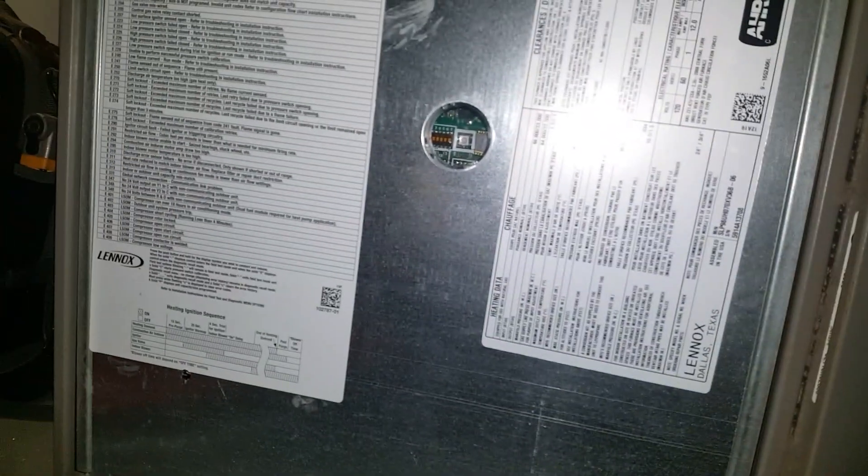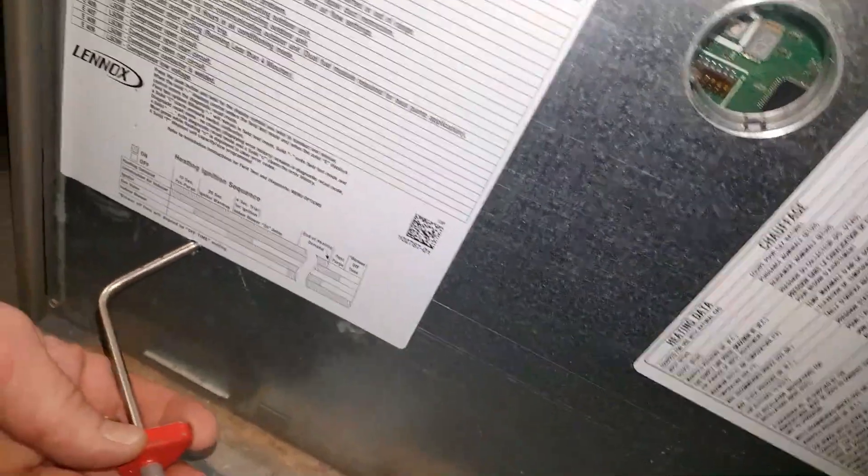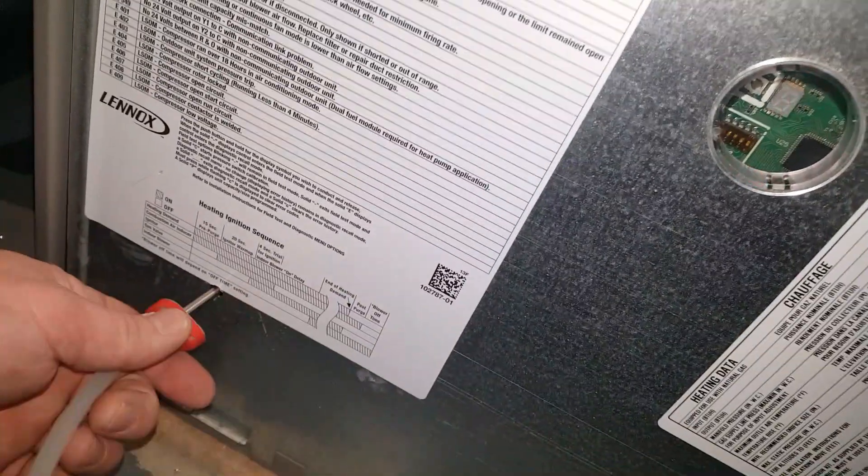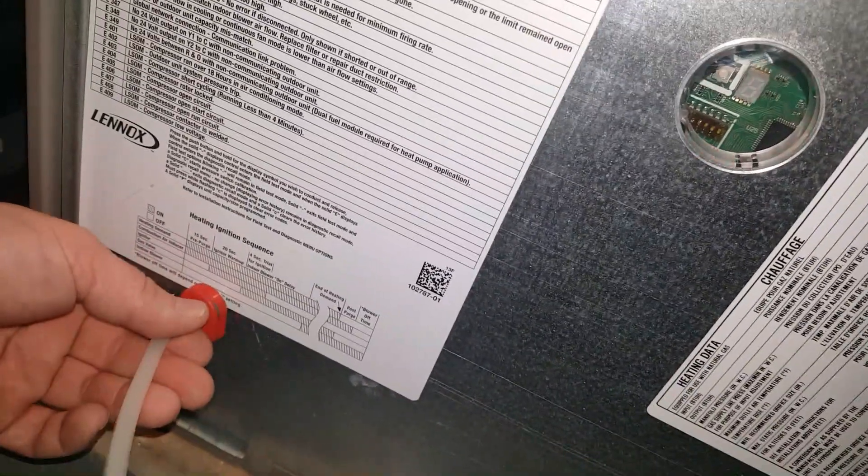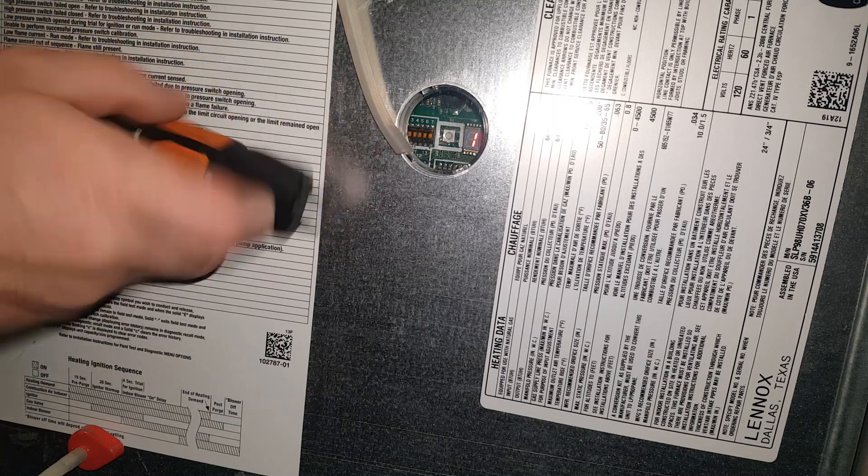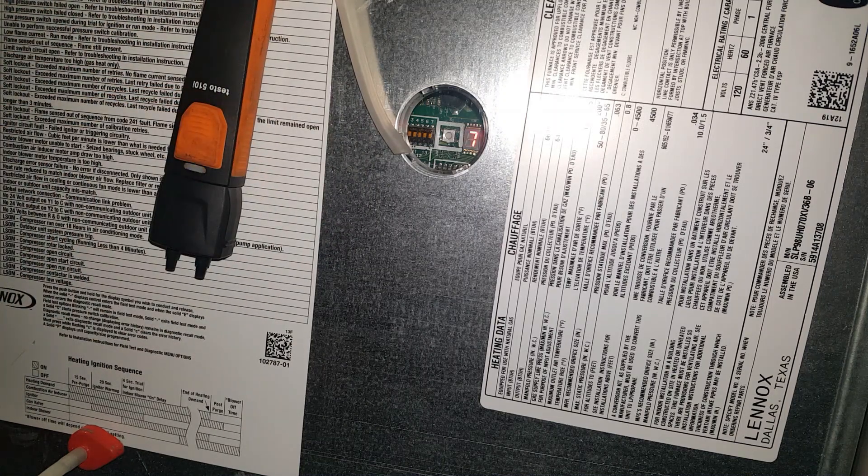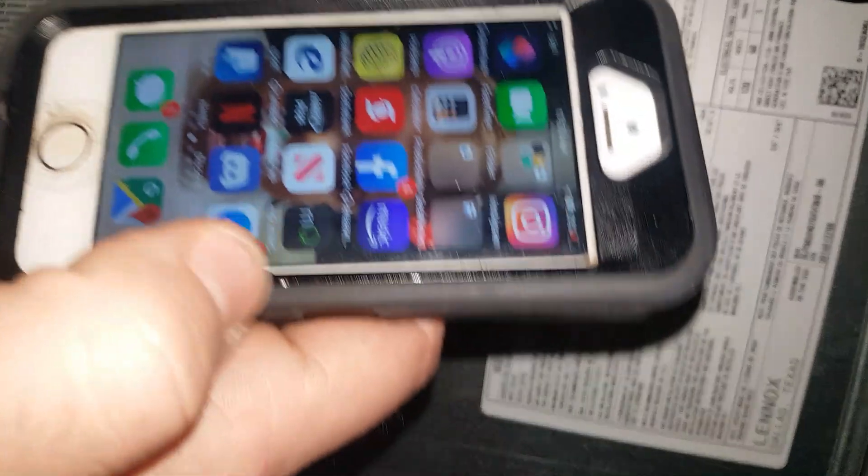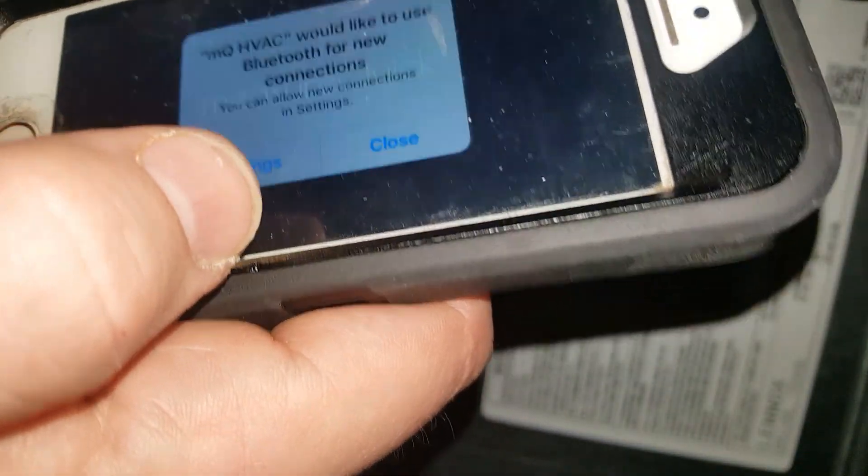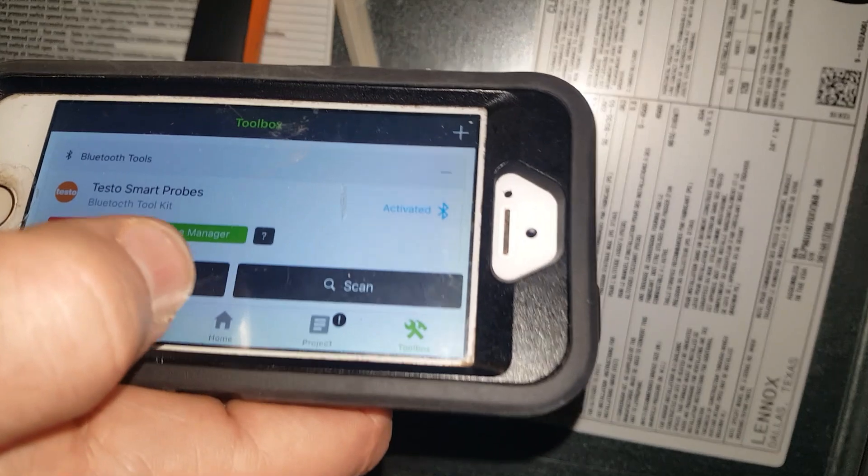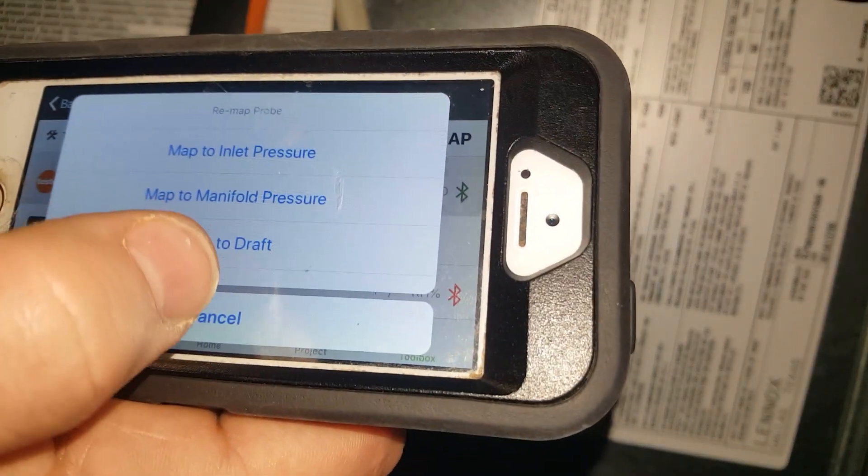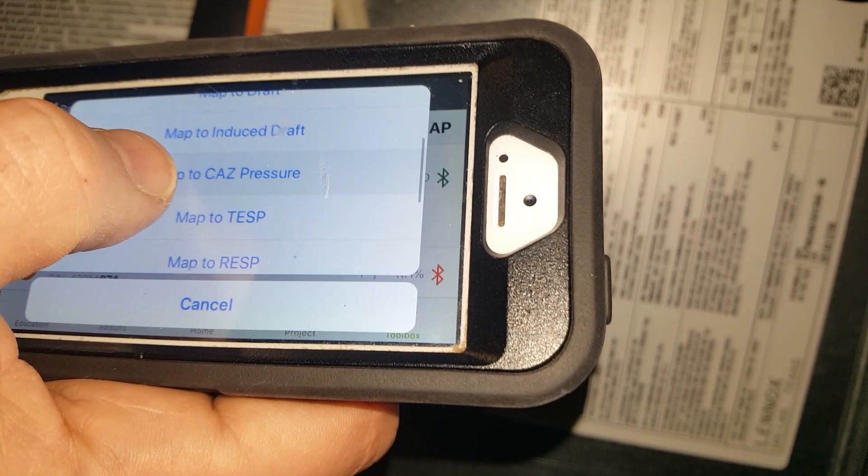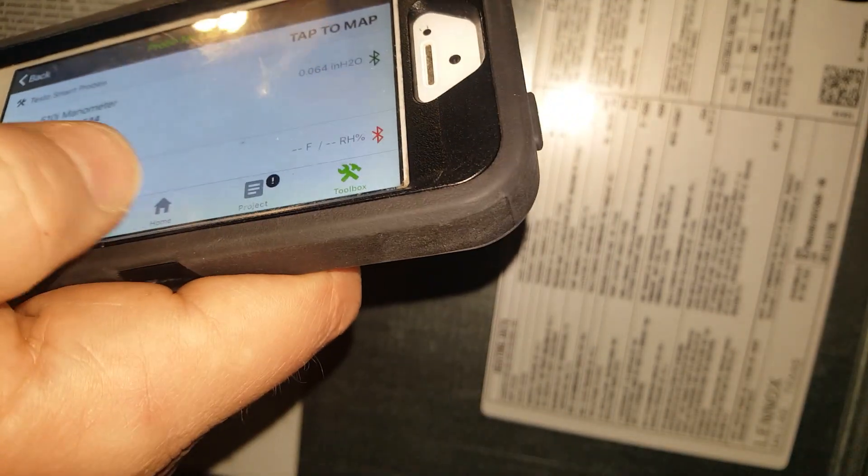The first thing I will check is my total external static, which tells me the entire system pressure. I'll put one of my probes there. Probe goes in right before the evap. Today I'm going to use Measure Quick for my reporting. I'm going to activate my probe manager and switch this over to total external static.